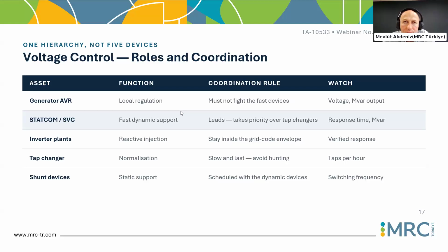Some countries have experience replacing or rehabilitating aged thermal power plants, dismantling or separating the turbines from the generators and converting them to synchronous condensers, which also provide this service in the grid without any fuel or mechanical prime mover at the back of the power plant. STATCOM and SVC are similar, not the same, but they are power electronic based devices. They have fast dynamic support. The main difference is that the SVC has voltage dependent support. If the voltage is depressed, the SVC's reactive output is depressed also, but the STATCOM's is not. STATCOM has a wider range of regulating capability. It's a power electronic device, very fast in response, in a couple of milliseconds, and it supports reactive power similar to a synchronous condenser, but we do not have the synchronous rotating inertia kinetic energy stored at STATCOM scale here.